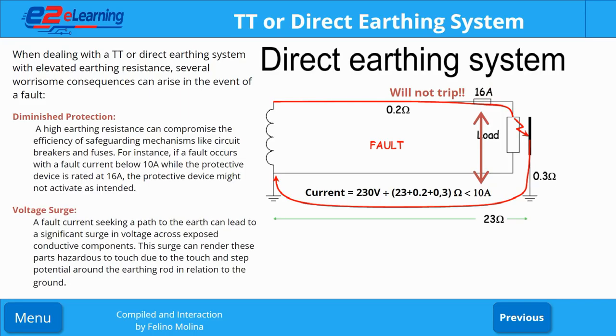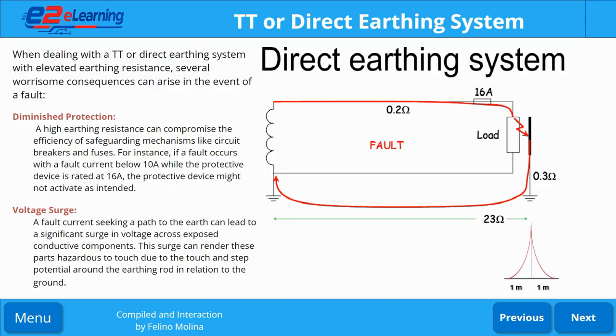A fault current seeking a path to the earth can lead to a significant surge in voltage across exposed conductive components. This surge can render these parts hazardous when touched, due to the touch and step potential around the earthing rod in relation to the ground.